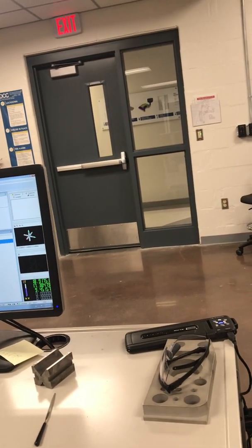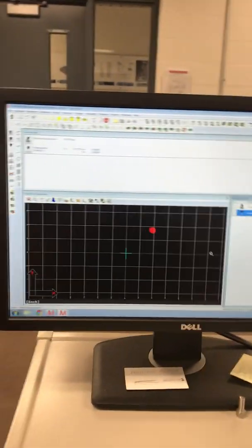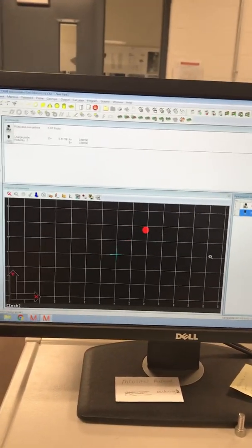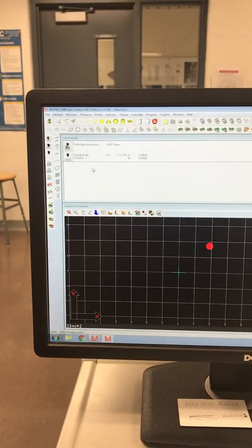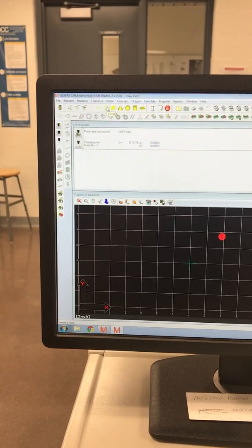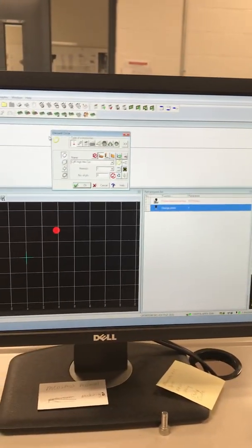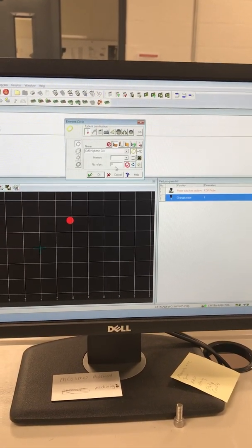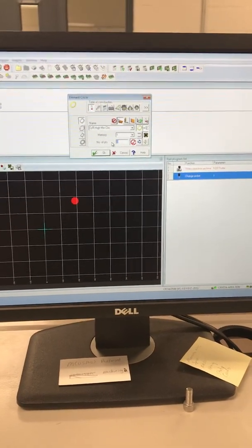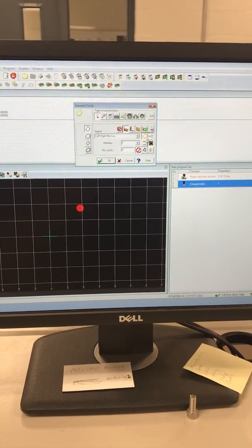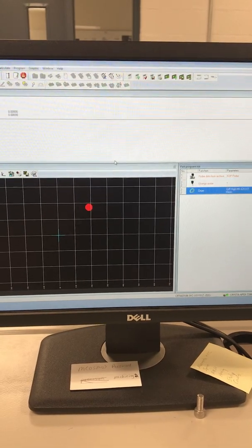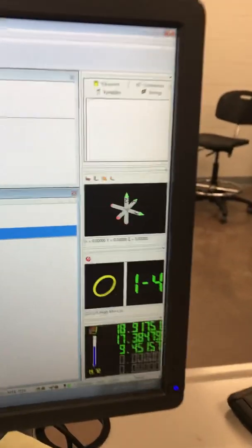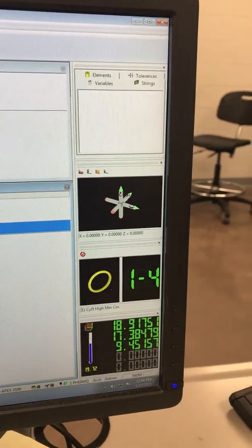Then the sheet says we can measure this thing without doing a major setup. If we just want to bring a part up in here, we can measure it. Let's just say we want to measure a circle. Now it may not be as accurate as if you do an alignment, which we'll get into later, but you can measure simple things. So let's just measure a circle. Right now it is set up for 8 hits. Let's change that to 4. And automatic, I don't want that. Hit okay. Now, this is telling you it is waiting on hit 1 of a circle.